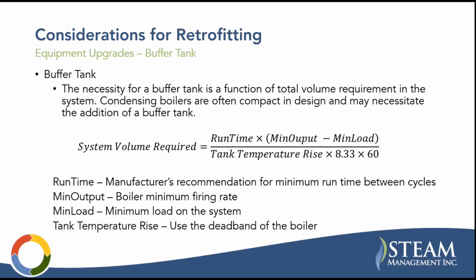The necessity of a buffer tank is basically a function of the total volume in the system. So this is the calculation for that. Your system volume requirement is based on your runtime, which is a manufacturer recommendation for the minimum amount of time between cycles on your boiler. You multiply that by the minimum firing rate of your boiler minus your minimum anticipated system load. If you don't know your minimum anticipated system load, you can assume 0 for that number, and you'll just get a conservatively sized system volume requirement. Your tank temperature rise is basically the deadband of the boiler, so the temperature it cuts off minus the temperature it cuts on. And then that'll give you your total system requirement. You subtract from that your estimated system volume, and that will give you the buffer tank size that you need.